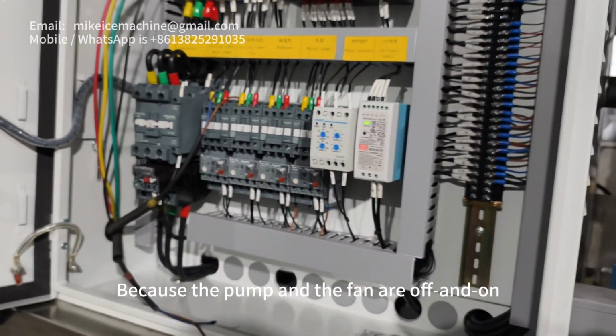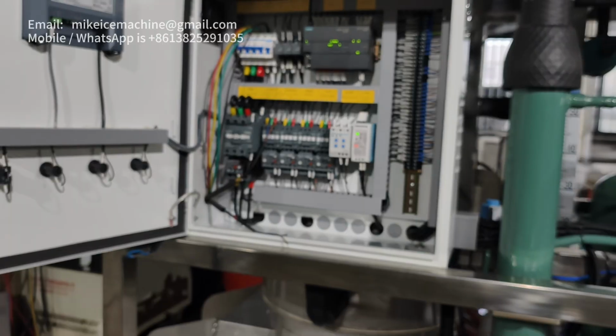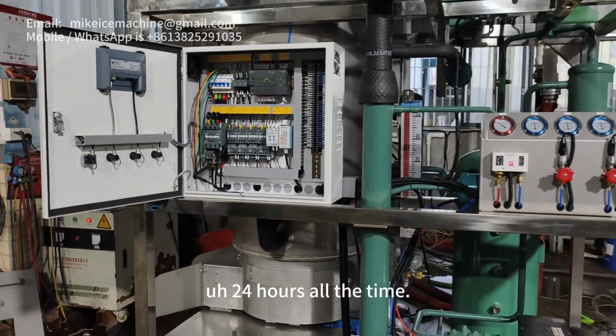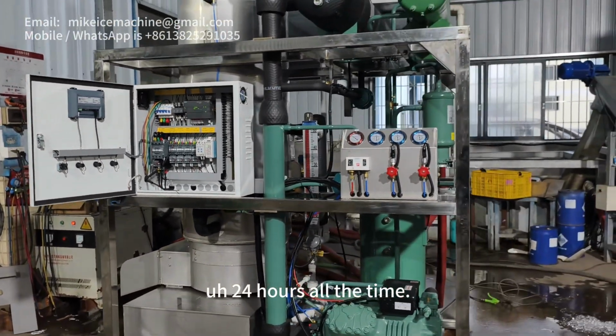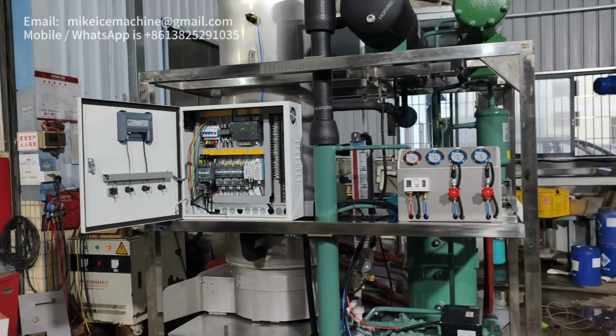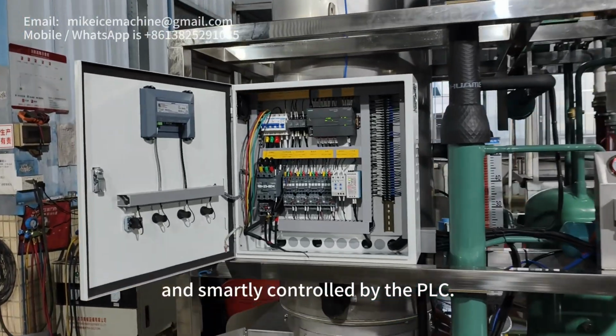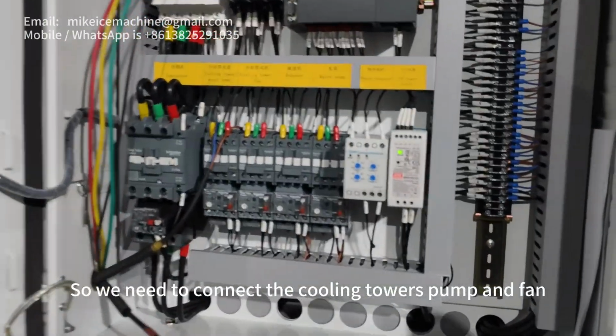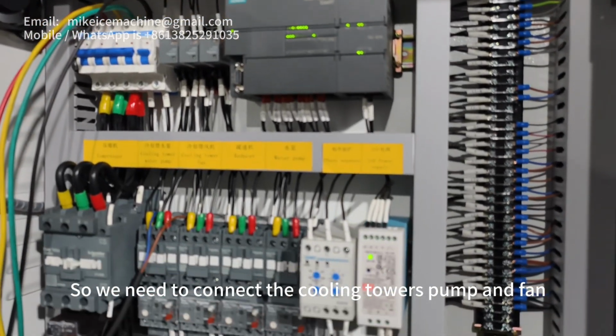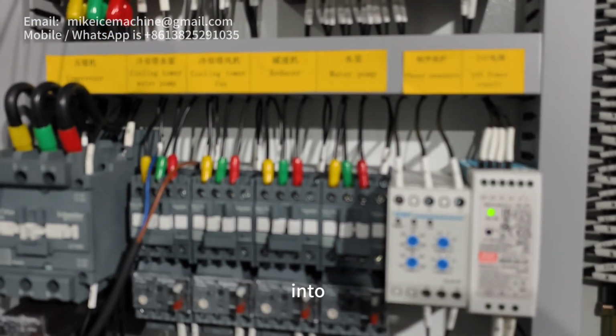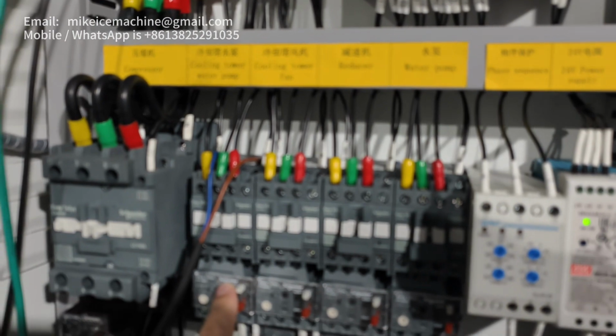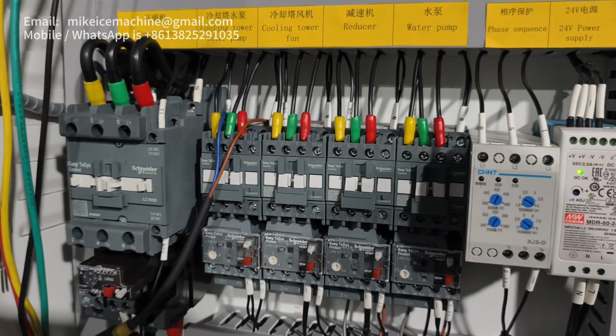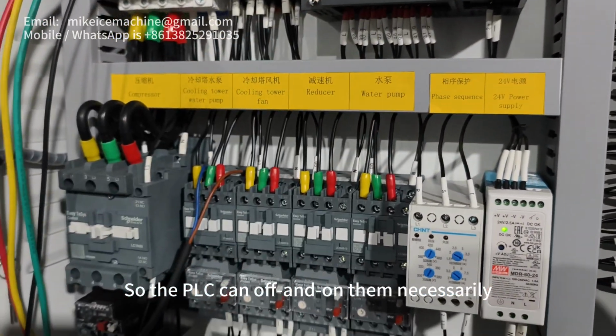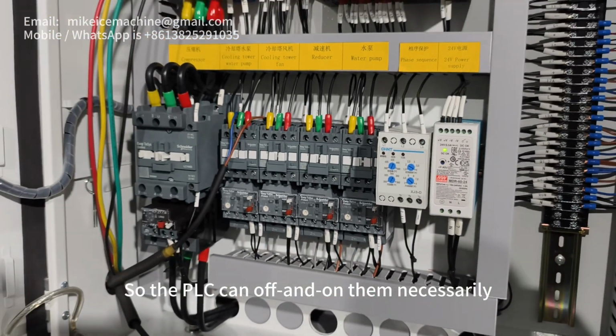Because the pump and the fans go off and on, they are not working 24 hours all the time. They should be switched off and on, smartly controlled by the PLC. So we need to connect the cooling tower's pump and the fan into this thermal relay, so the PLC can switch them off and on as necessary.